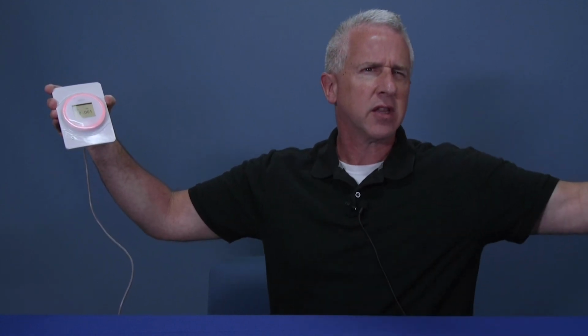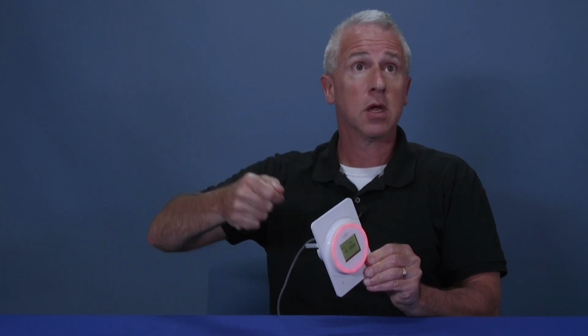I don't have to walk up to be within inches of it. So I literally get economies of scale if I still want to do a manual check on different pressures in different spaces. But number two, I have an analog output. So I can continuously, immediately connect this to a network or connect this to a Setra Flex room monitor, and my room monitor will be connected to my building automation system.